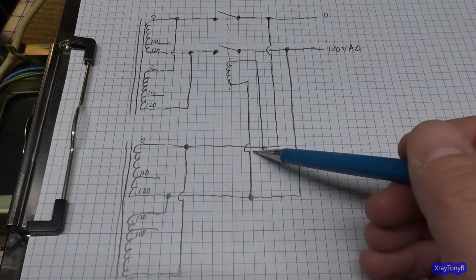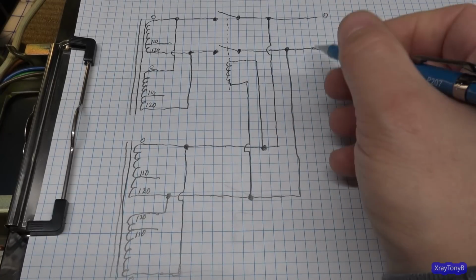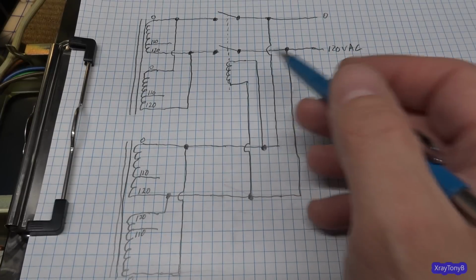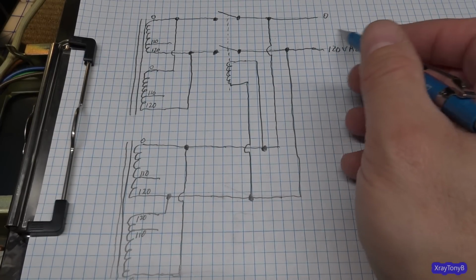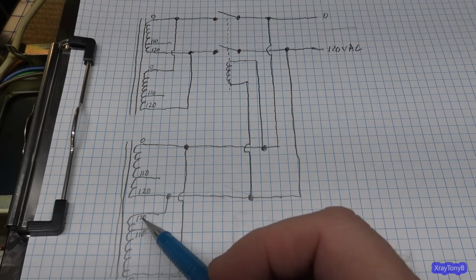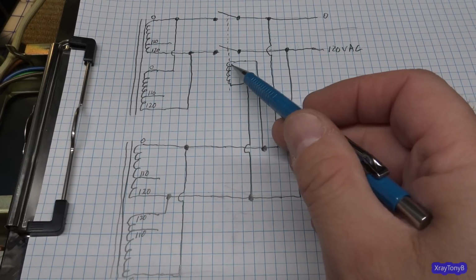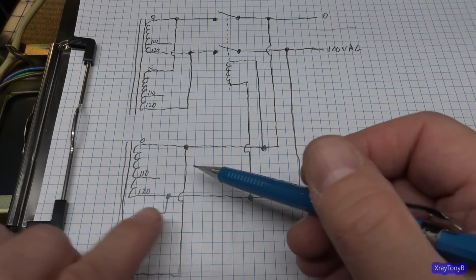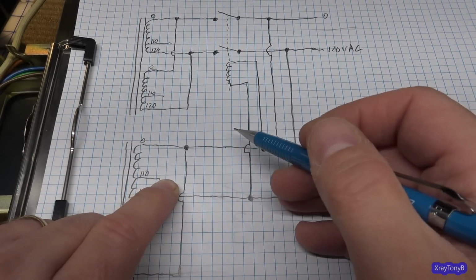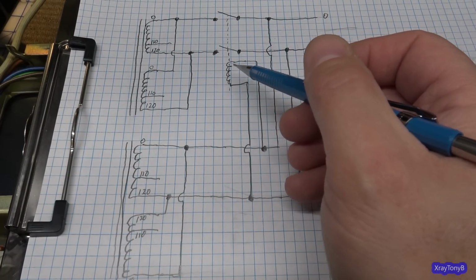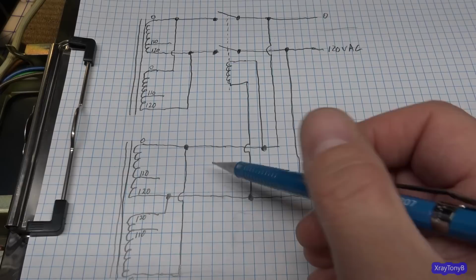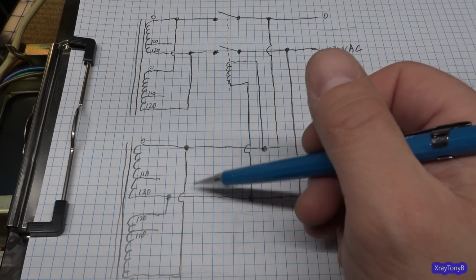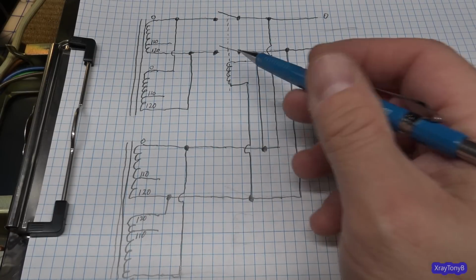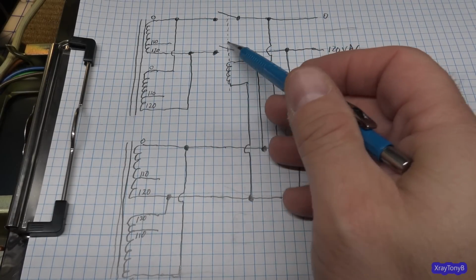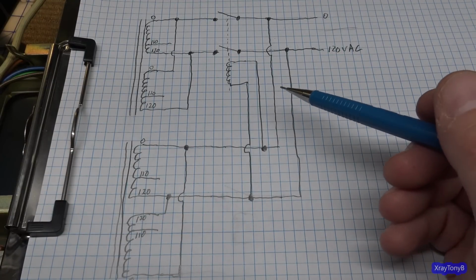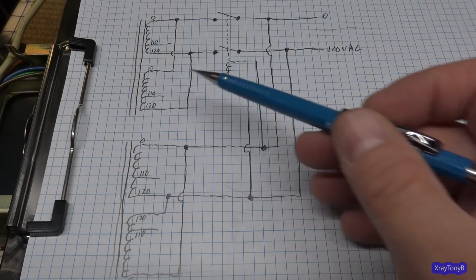Here's your relay, and it's still just shunted right across your mains. So your mains voltage comes down into here, and this is across it. When you turn the power on here, this will come on right away, and then after a slight delay, while this energizes and pulls in, this one will pull in. That ensures these things aren't starting up on the same cycle. Because this probably takes about 8 milliseconds to pull in, whereas this starts right away, so you'll have about 1 or 2 cycles, or half a cycle, before this one pulls in. So you're still putting a lot of inrush current in doing it this way. This isn't a very good solution for a soft start circuit.